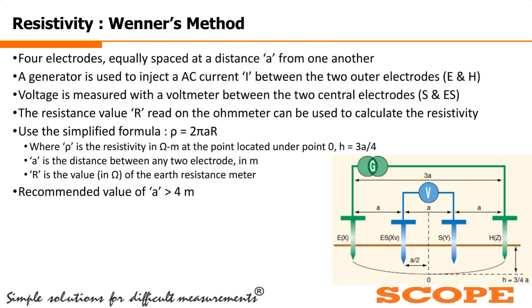For that, four electrodes are used. In Wenner's method, four electrodes are equally spaced at a distance A. There is a generator which is used to inject current I between the far end terminals, that is E and H, and voltage is measured between terminals S and ES. In this way, the resistance value is measured on the instrument, and with the help of a simplified formula, rho equals 2 pi A R, we calculate the earth resistivity.